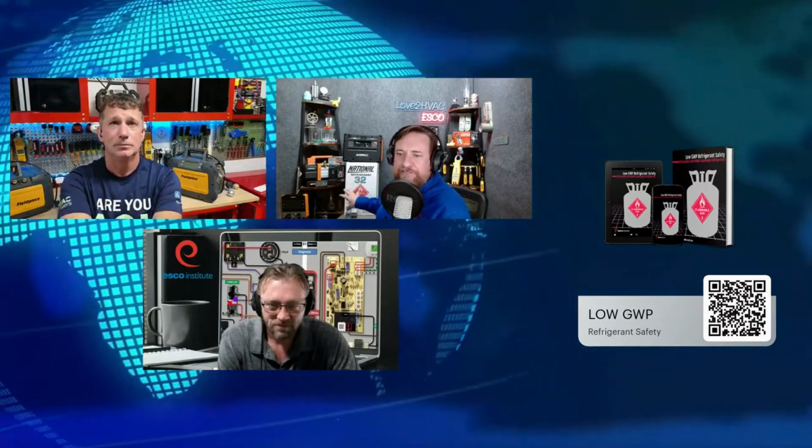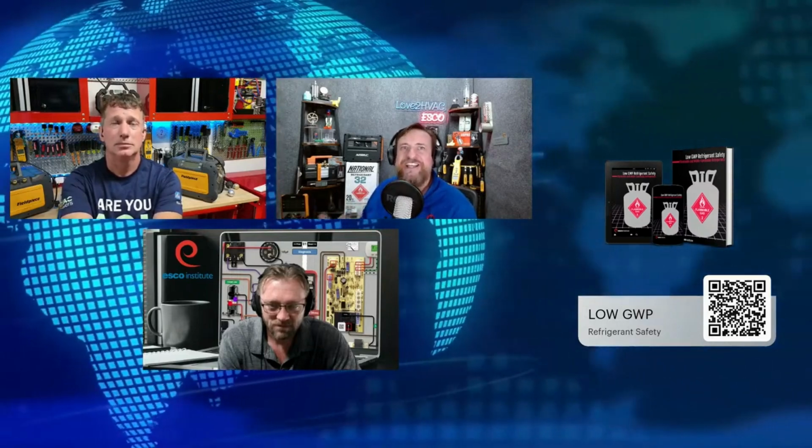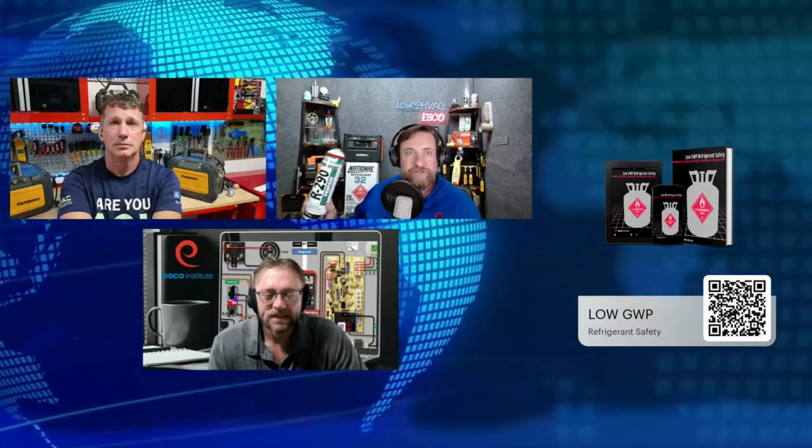So if you're not doing those safety practices, you have some of those methods that were bad long ago, like just purging. Those are situations, and also in other countries, they're known to use propane and even methane in refrigeration systems. So when you see those videos and people are sensationalizing those, that's a whole different complex. And actually, if you look now, most of the new refrigerators sold are isobutane, R600A, which is an A3 highly flammable refrigerant. And they're in refrigerators all over the country.